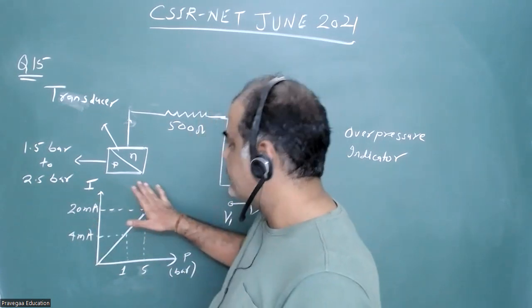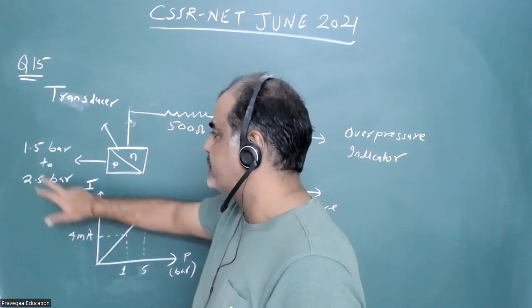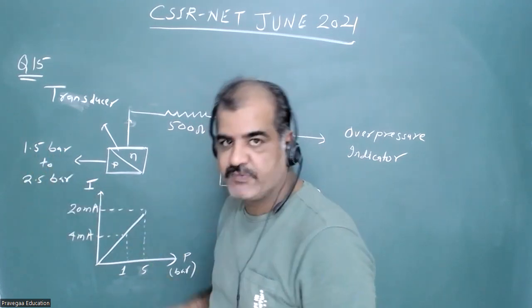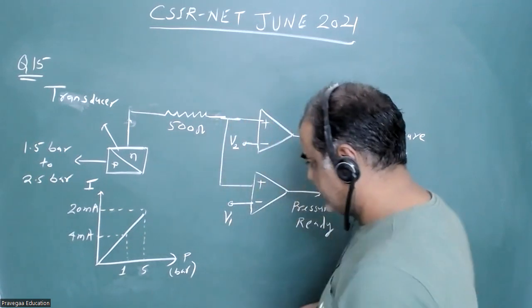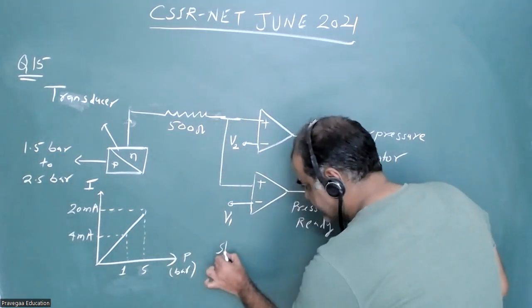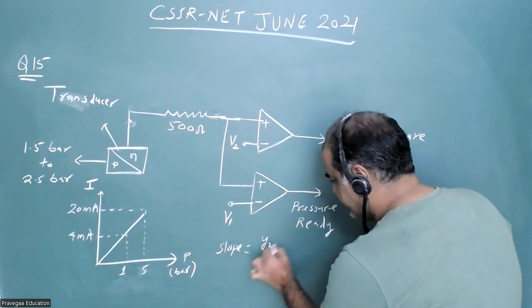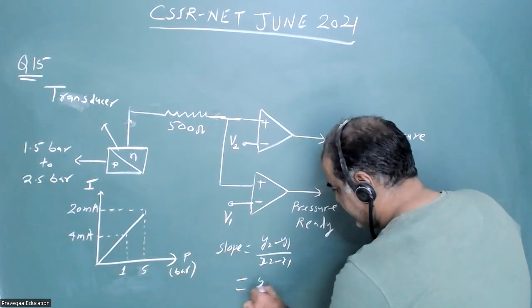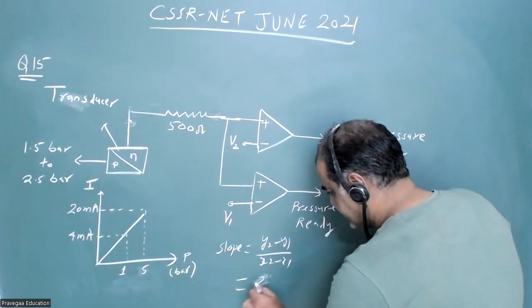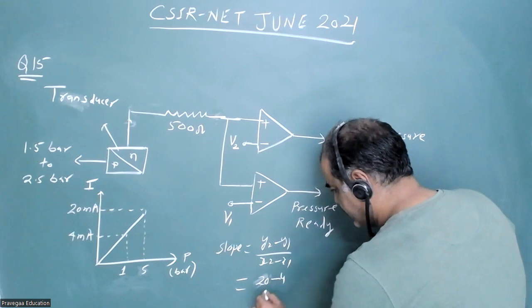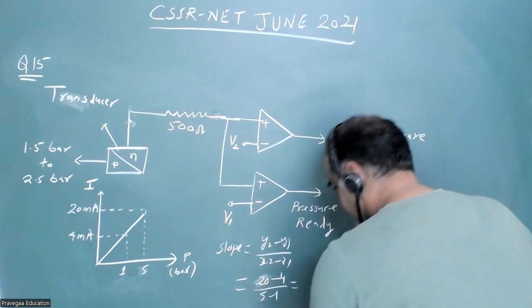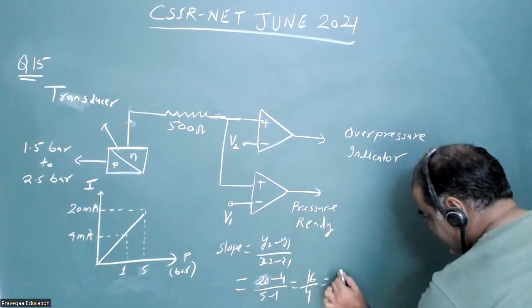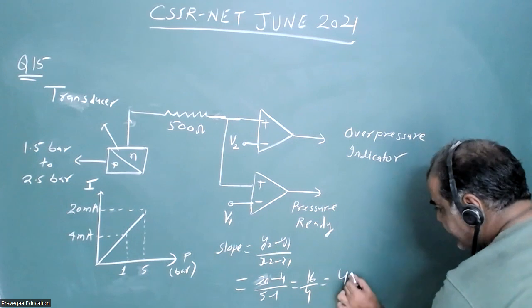We have to maintain pressure from 1.5 bar to 2.5 bar in this experiment. The slope of this graph is (y2 - y1) / (x2 - x1), that is (20 - 4) / (5 - 1), which gives us 16 upon 4. So the slope of this graph is 4 milliampere per bar.